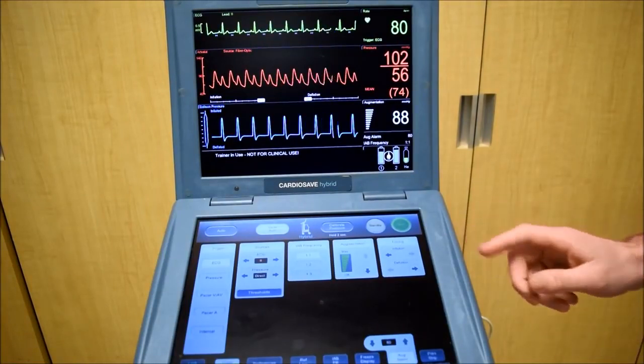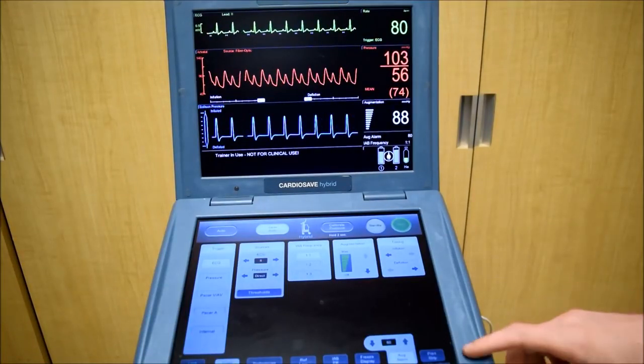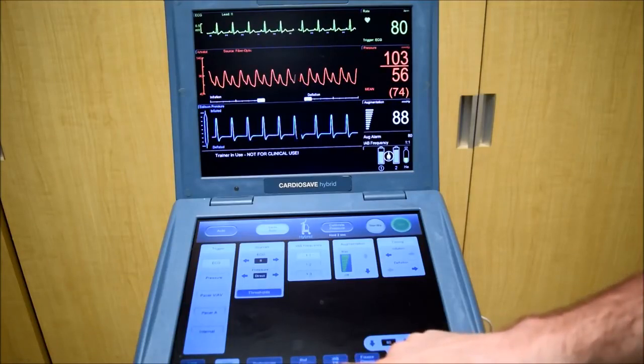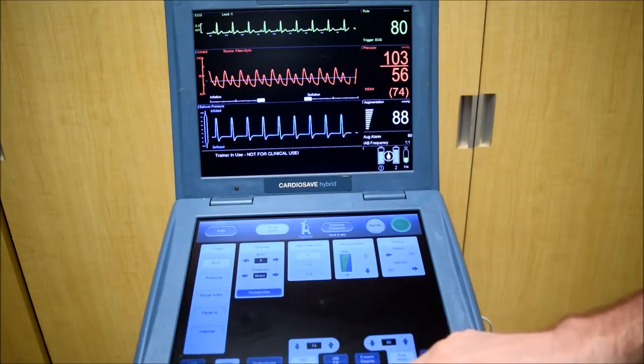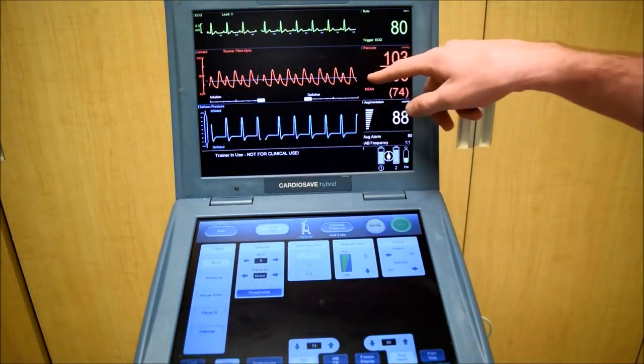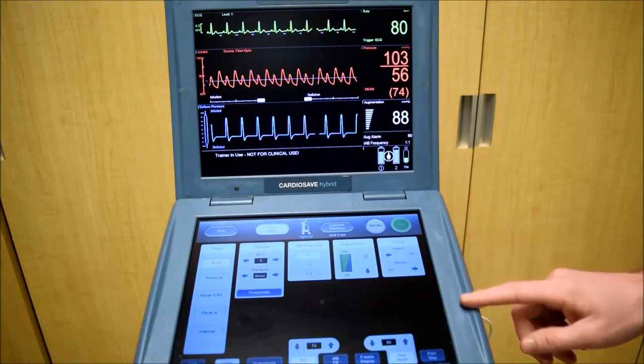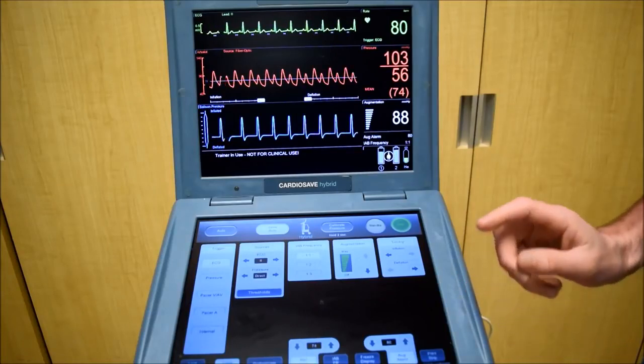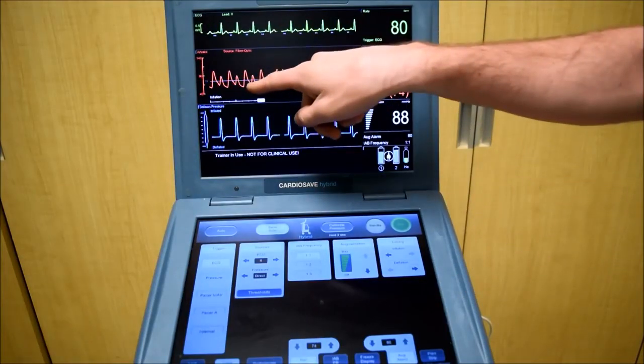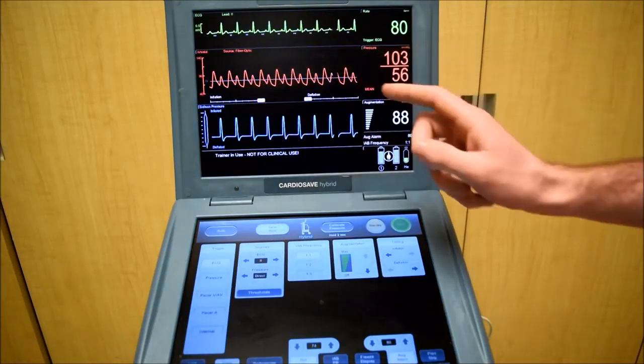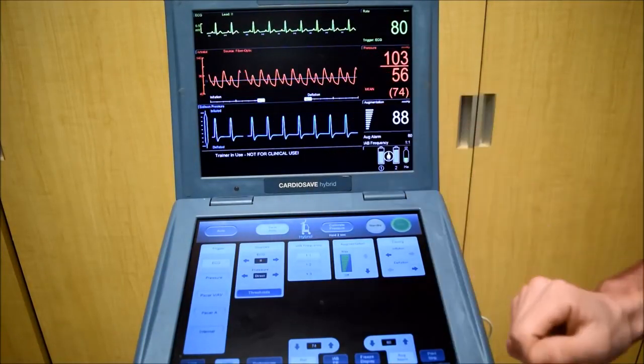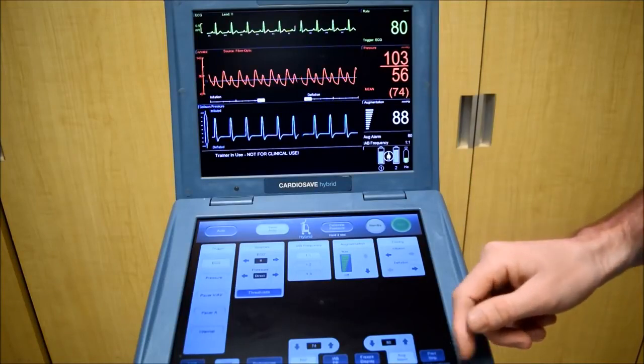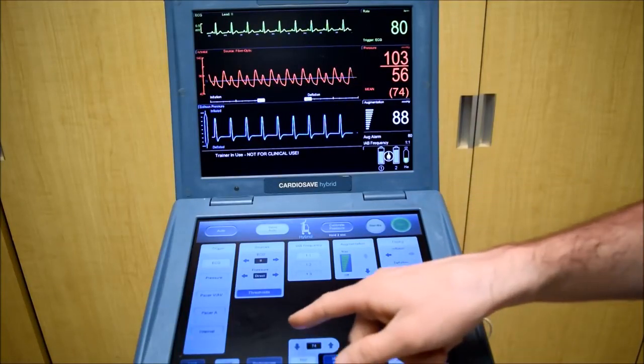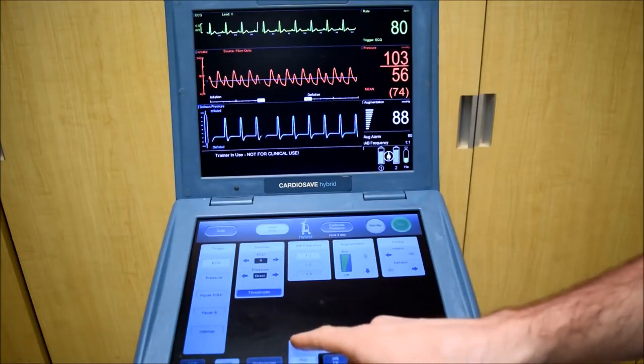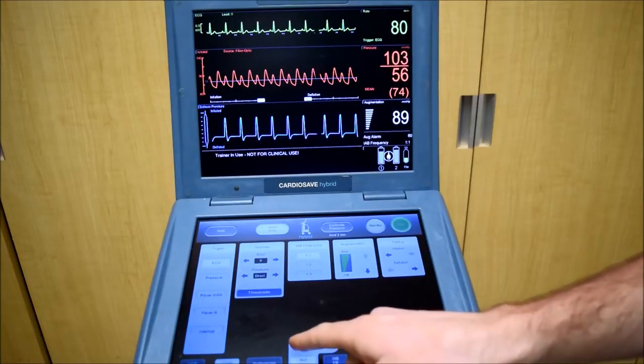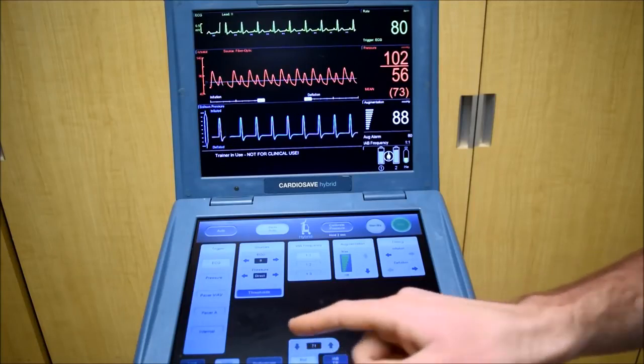Okay, let's adjust our inflation first. In order to do this, I'm going to use the reference line. That's on the bottom here. Now this brings up a line that runs across our pressure trace. What we want to do is put the inflation of the balloon right at the dicrotic notch of our pressure trace. So I'm going to move the reference line to be right on our dicrotic notch. I'm going to adjust it down right about there.